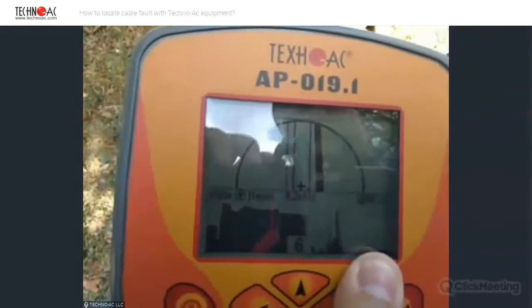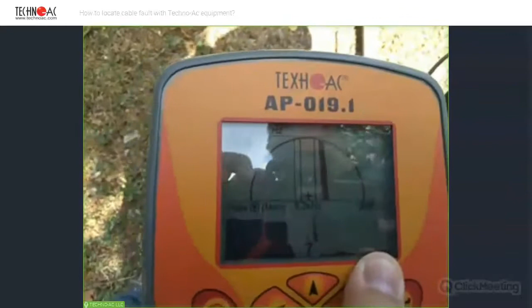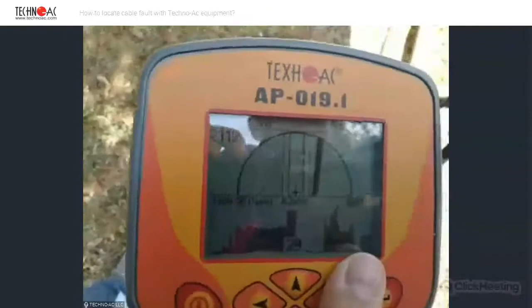The signal almost completely disappears. It means that we have located something, the place where the electric current from the cable is leaking to the ground. If we move the sensor 1 meter forward, you can see that the signal will increase. Again, it will increase. But when we place it right above the supposed position of the fault, make sure that you have stuck, it will almost completely disappear.